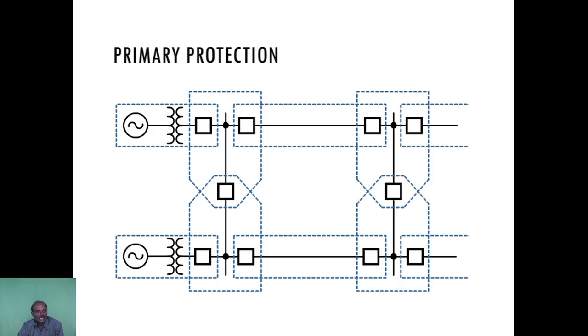So protection involves circuit breakers and the relays. Relays are energizing the circuit breaker whenever we have the fault in order to isolate the components of the system. So after the clearance of fault, we have to reclose the circuit breaker. That is also involved by the relays. The main purpose of protection element, we have the relays and circuit breakers connected with the relays. So energizing the circuit breakers or operating the circuit breakers, the relay is involved to isolate or reconnect the faulty equipments with the system.